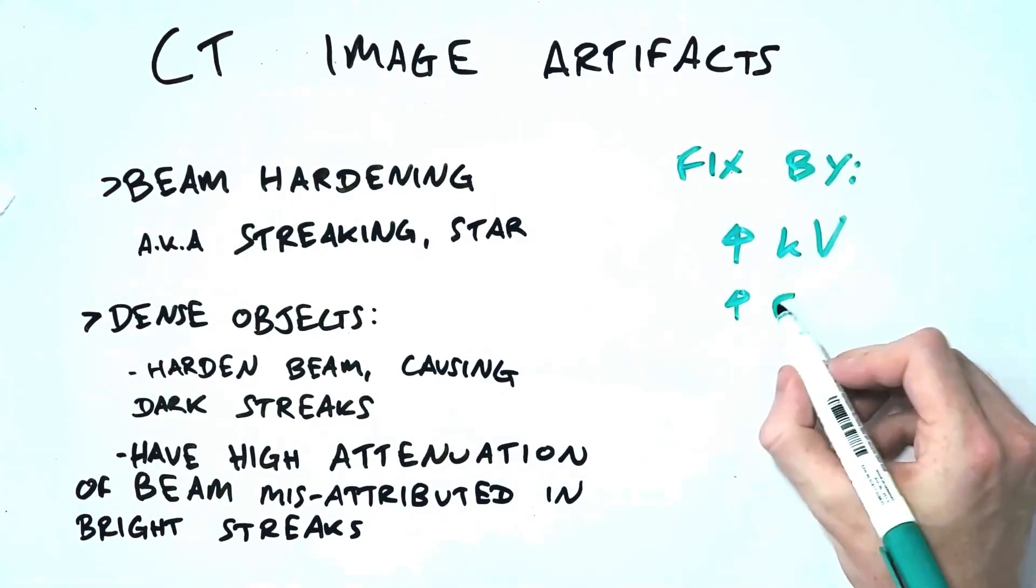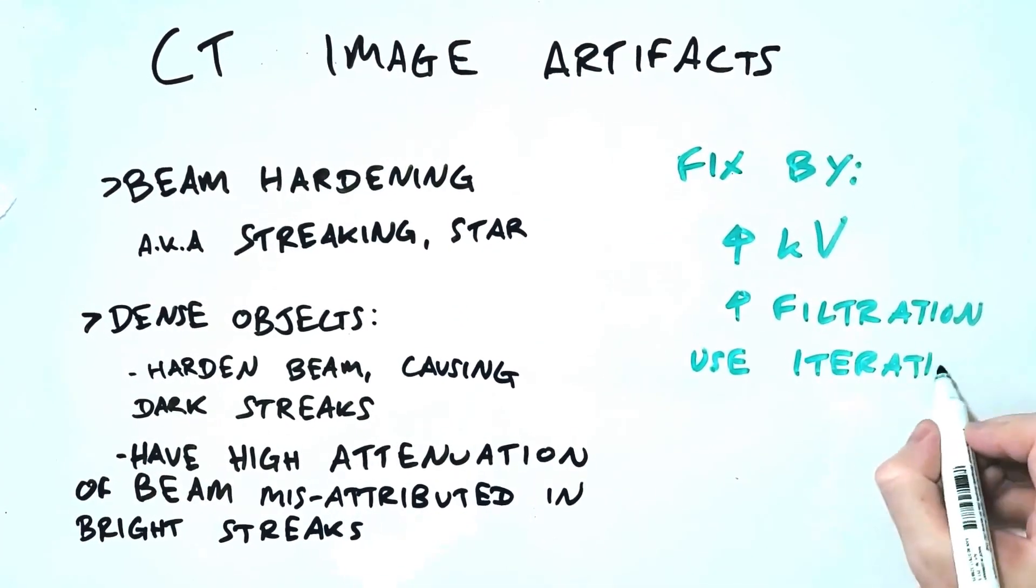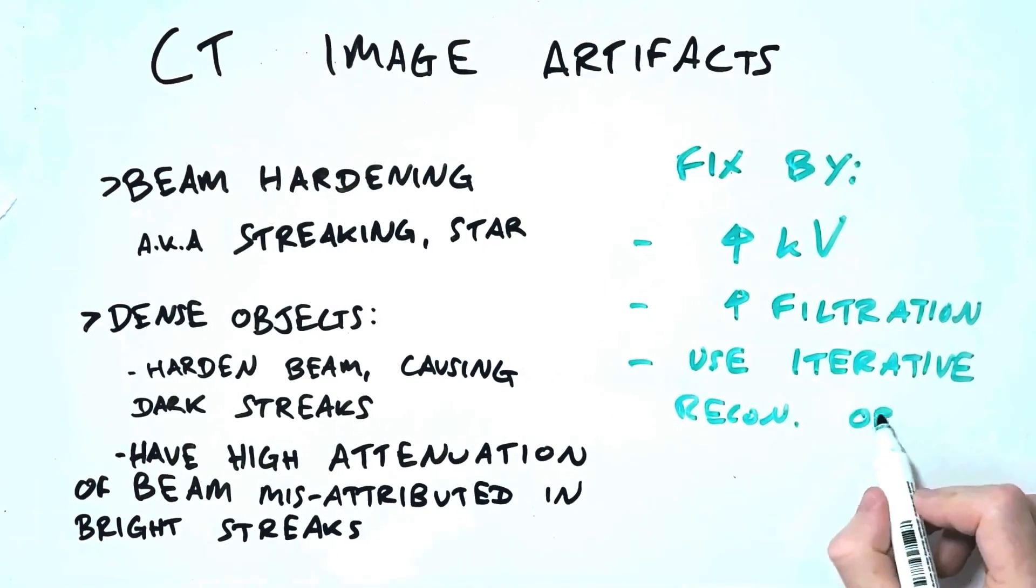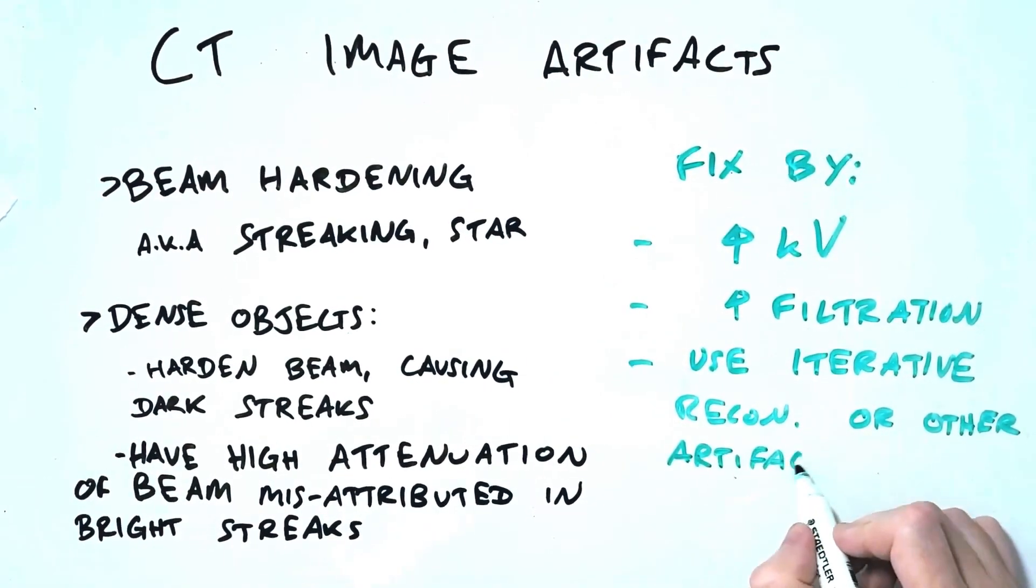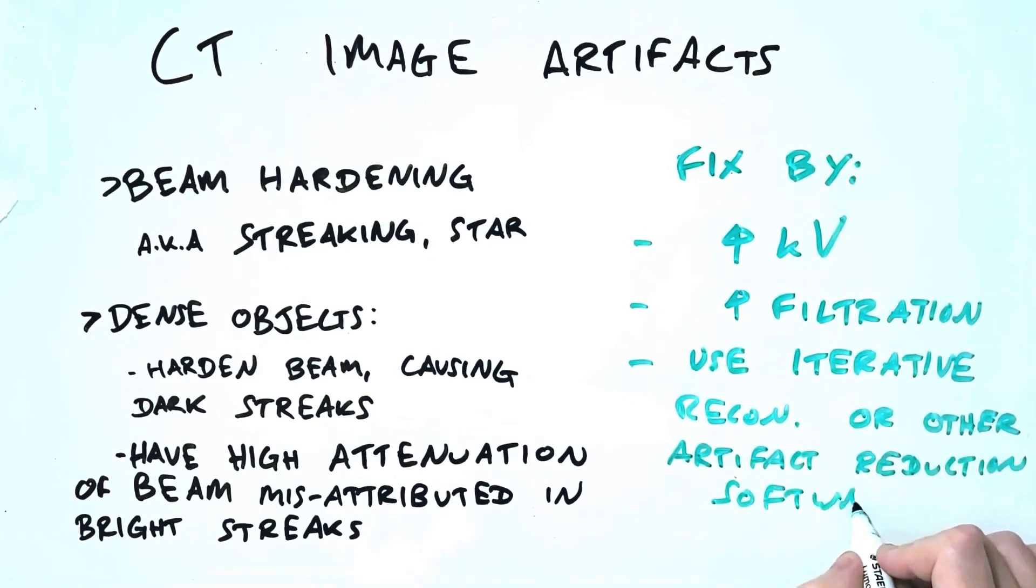This artefact can be decreased by using a beam with a higher average energy, either through increasing the KV or using filtration. Using iterative reconstruction or artefact reduction software can also be very effective.